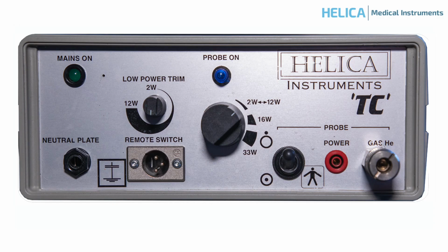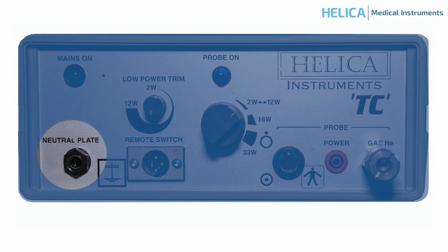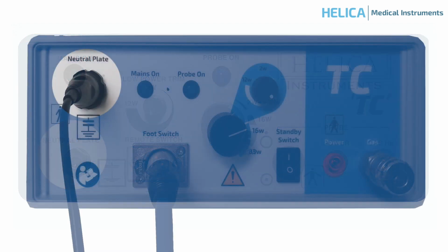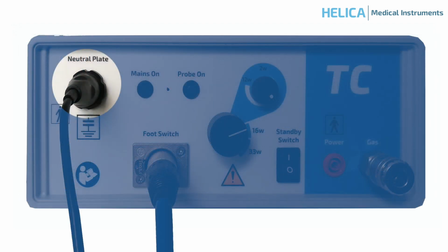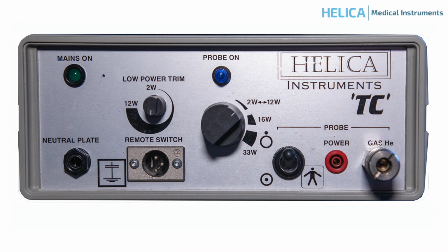On the front of the machine, there's a panel which accommodates the main controls. On the left, there's an earthing lead socket. An earthing lead with a 4 mm jack plug connection is supplied for the patient's safety. This is for use in a standard earth plate. New instruments have a reusable magnetic connector for a standard earth plate, as shown. Above this, there's a power on-off green light indicator. The main power switch is at the rear of the unit.